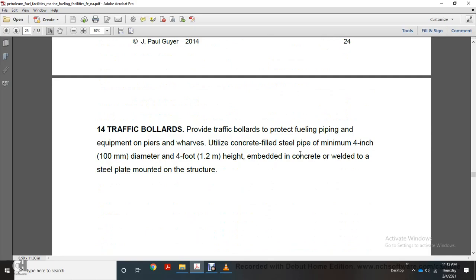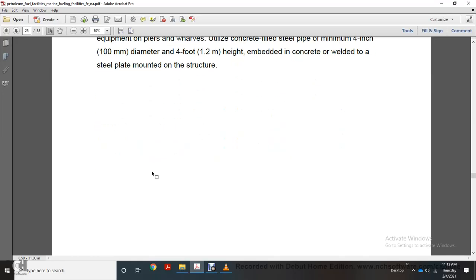14. Traffic bollards. Provide traffic bollards to protect fuel piping and equipment in the way of traffic. Use concrete-filled steel pipe, minimum 4-inch diameter and 4 feet in height, embedded in concrete and welded to a steel plate mounted on the structure.